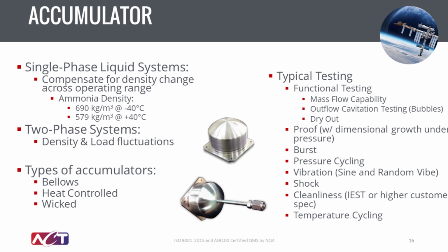There are several different kinds of accumulators. The one you see in the picture here is a bellows-style accumulator, which can expand as the fluid volume requirement goes up and retract as it declines. There's also heat-controlled and wicked accumulators, especially useful for two-phase solutions where you want to ensure that all your vapor is contained and trapped in the accumulator and that any pumping mechanism will not see any liquid vapor. And then on the right side, you can see a short list of a lot of the testing that goes into these. So these go through pretty lengthy and elaborate qualification and acceptance testing, making sure that they are flight worthy at the end of the day.